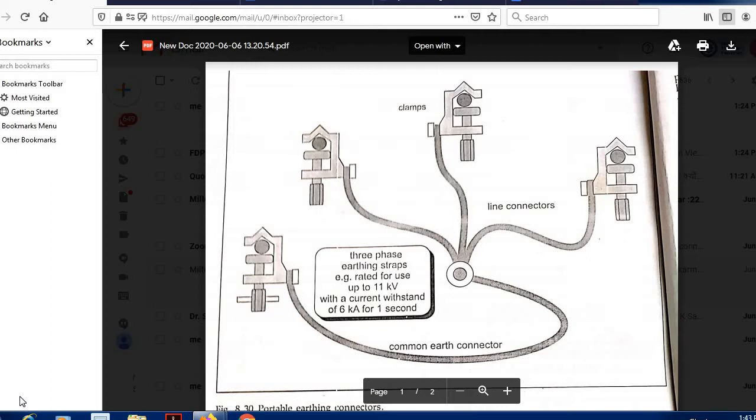Means the second section requires that the circuit has to be totally isolated, means dead, and dead includes the deactivation of those storage devices like capacitors and all. So isolated and de-energized, and then it is connected to the earth.